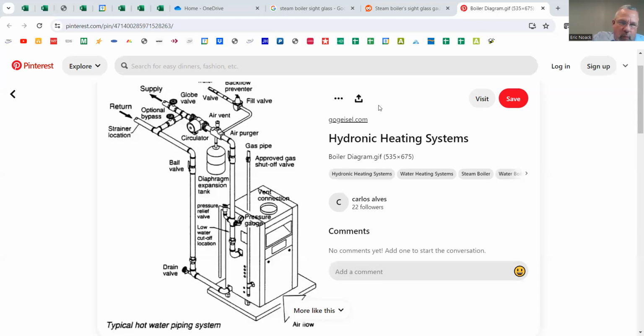So your water supply comes in at the very top of the screen where you see fill valve, and that pipe takes a turn and goes directly into the air vent. That's the best way to pipe it, from my perspective. When you have an air eliminator, it's there to pull the air out of the water, and it's a really important part of a boiler system. What happens when you put water into a boiler is that the water we get from our tap is aerated. It's got air in there. There's an aerator on the sink. There's air in there, and generally there's air entrained in the system.